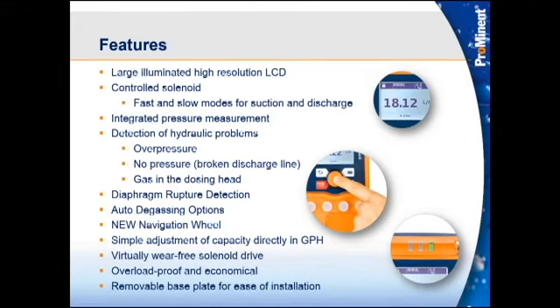How that works is if we're pumping against pressure and the pump's pumping like it should, everything's going good, all of a sudden it's taking more energy for that pump to work as it's going. All of a sudden it's harder for it to do, meaning it has to make more energy to do that. That most likely means we may have a blockage in the line. Somebody may have come up and shut a valve somewhere. It's harder for that pump to pump. So we go into what we call a P plus error. That's an overpressure, just like the Delta. Kind of along the same lines, if we're pumping normal, all of a sudden it's taking less energy for us to pump.